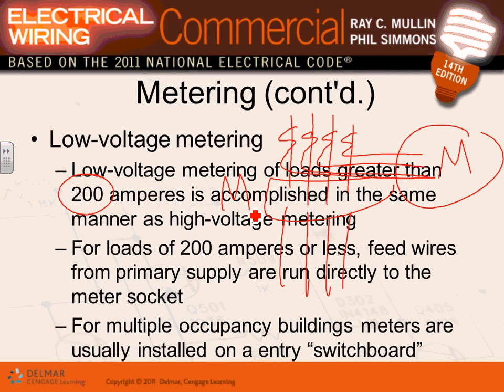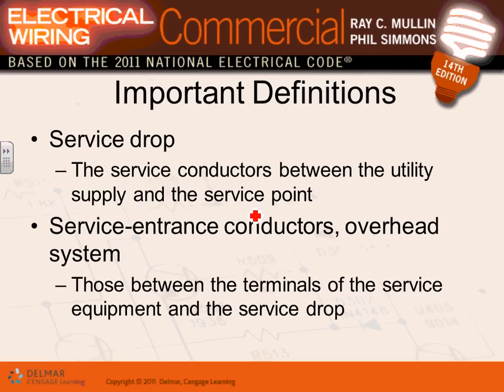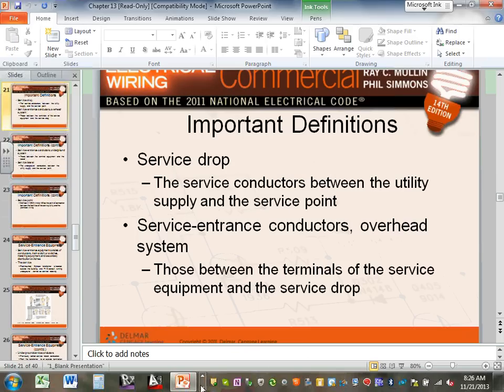So that's my metering. Any comments, guys, about the metering? All you need to know about the commercial project is if you go higher than 200 amps, which ours was 500 amp, you have to do CTs and pull these CTs into a meter. When you bring your service to the building, guys, I want to show you a couple of pictures.